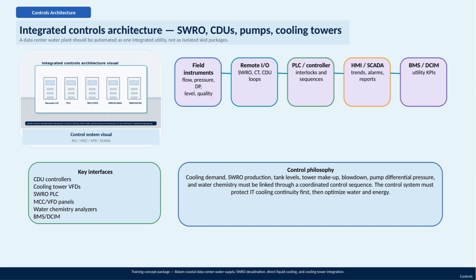On a higher level, the building management system and data center infrastructure management tools track key performance indicators, helping optimize utility usage. Key interfaces tie everything together. This includes CDU controllers, cooling tower VFDs, SWRO PLCs, MCC and VFD panels, water chemistry analyzers, and the BMS/DCIM systems. The control philosophy centers on linking cooling demand, SWRO production, tank levels, tower makeup, blowdown, pump differential pressure, and water chemistry through a coordinated control sequence. It prioritizes IT cooling continuity above all, ensuring no interruption in service, while simultaneously optimizing water and energy use for efficiency. This integrated approach is fundamental to maintaining reliable and sustainable cooling operations for the data center.